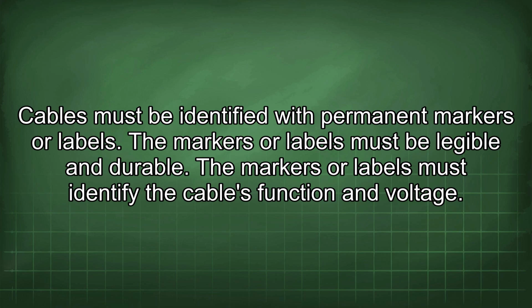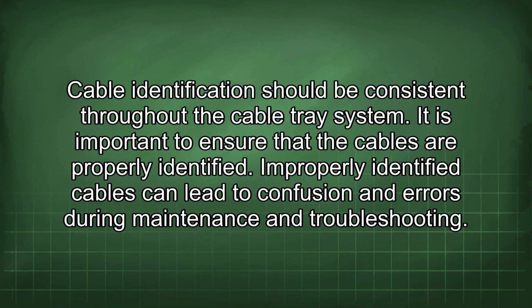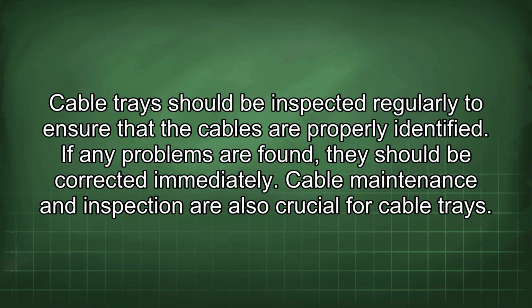Cables must be identified with permanent markers or labels. The markers or labels must be legible and durable. The markers or labels must identify the cable's function and voltage. Cable identification should be consistent throughout the cable tray system. It is important to ensure that the cables are properly identified. Improperly identified cables can lead to confusion and errors during maintenance and troubleshooting. Cable trays should be inspected regularly to ensure that the cables are properly identified. If any problems are found, they should be corrected immediately.